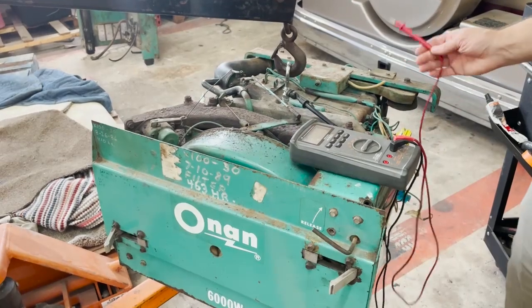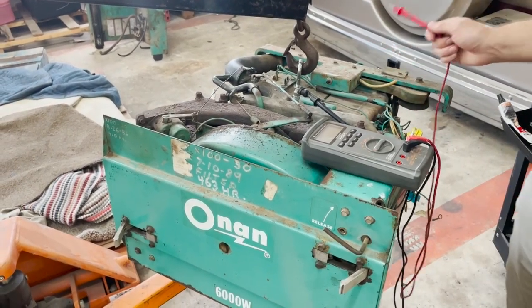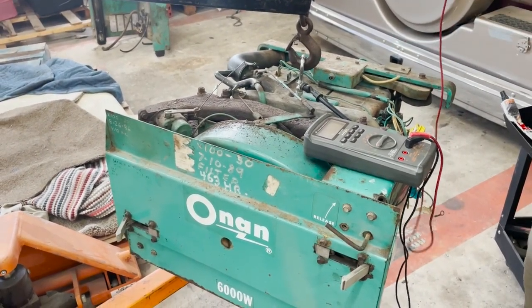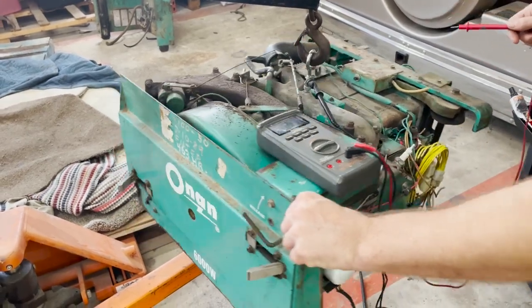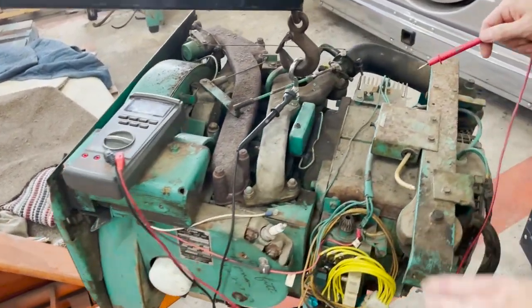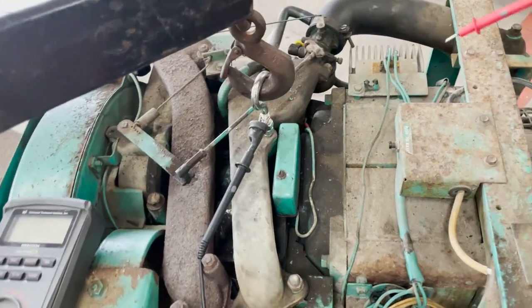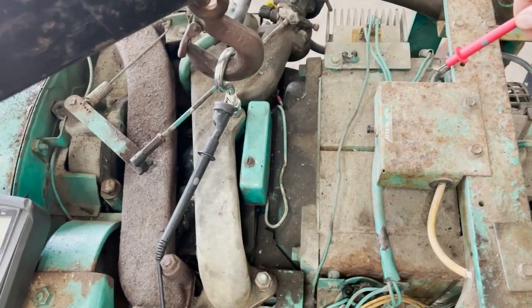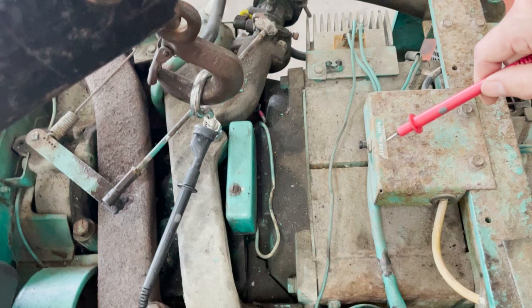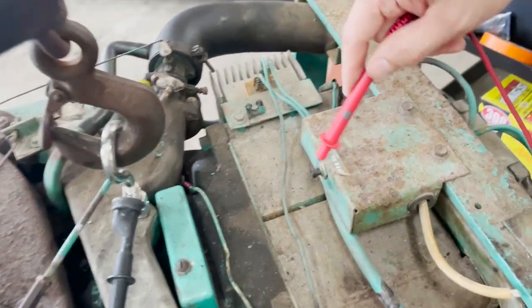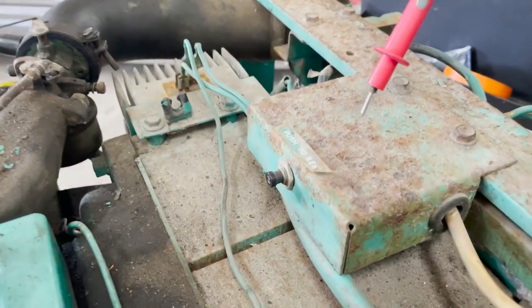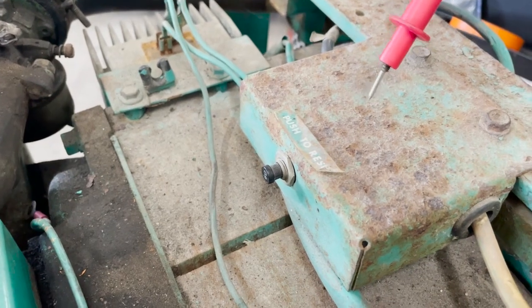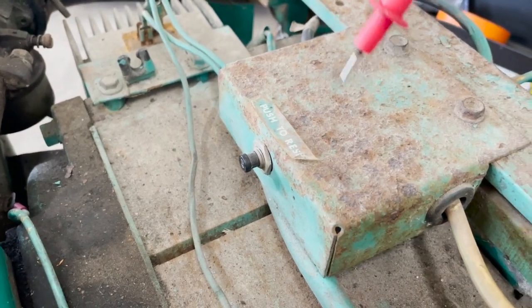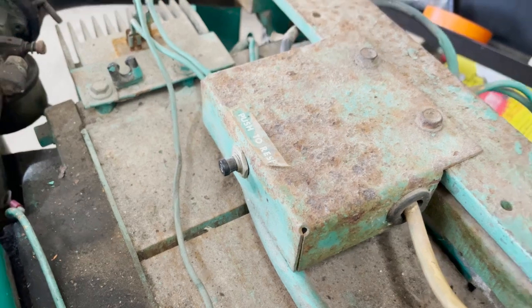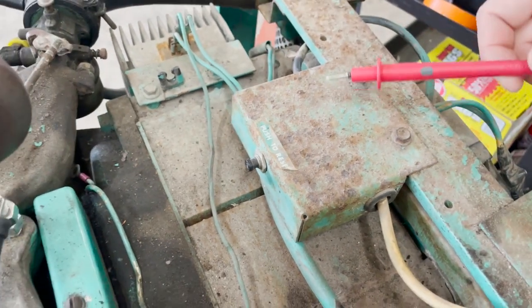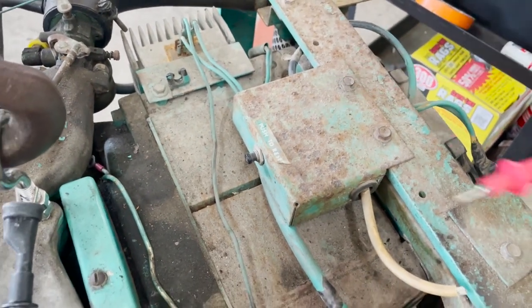I showed you guys how to use the multimeter to check if it's making voltage. Now I'm going to go a little more advanced. If you didn't see power on this side, but you are seeing power on this side, then try this push to reset—if you trip that, the circuit breaker might be tripped inside this housing, and you may even have to replace that circuit breaker. I don't know the part number on that. I haven't had to do one, but it is a possibility.